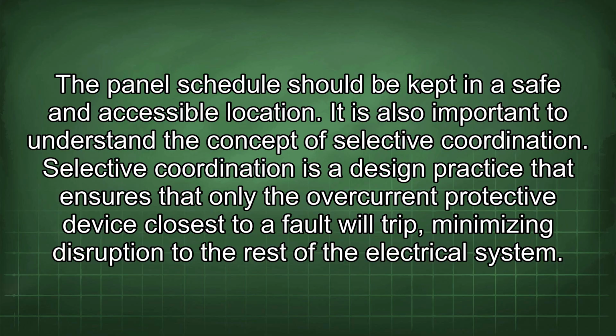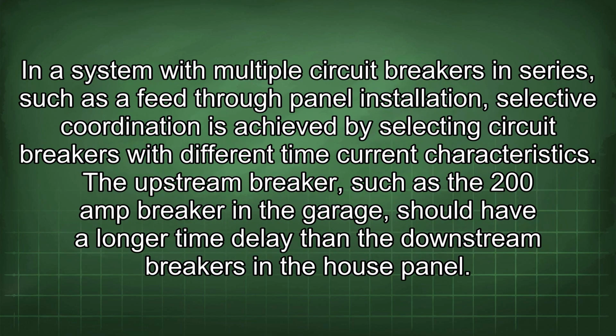It is also important to understand the concept of selective coordination. Selective coordination is a design practice that ensures that only the overcurrent protective device closest to a fault will trip, minimizing disruption to the rest of the electrical system. In a system with multiple circuit breakers in series, such as a feed-through panel installation, selective coordination is achieved by selecting circuit breakers with different time current characteristics.